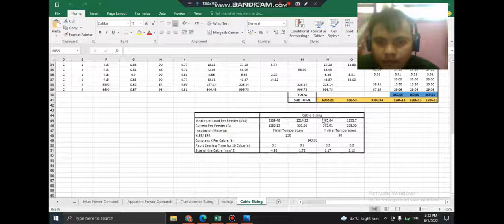And last, for cable sizing, the maximum load per feeder is 1155.7, the current per feeder is 359.55, the insulation material initial temperature XLPE is 90, and the constant per cable is also 143.08. The fault clearing time for the time cycle is 0.2, and the size of the cable is 1.12. Okay, that's all. Thank you.